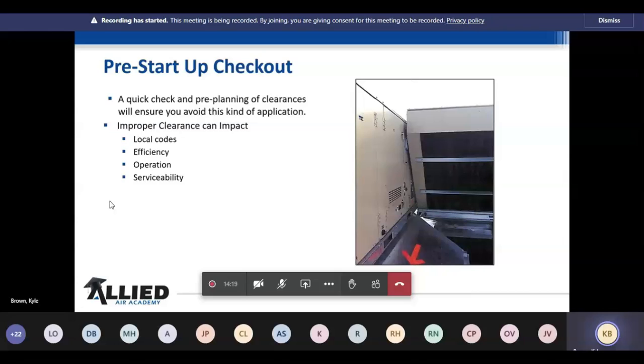So if, for instance, the instructions say you have to have 5 feet between these units, but the local code says 8 feet, then we're going to go by 8 feet. It's hard to get an inspector not to do that. And obviously the efficiency and the operation is going to go to you know what, but then there's the serviceability. These units are expecting to stay on these roofs 15, 20, 20 plus years, and they're going to need servicing on a regular basis.